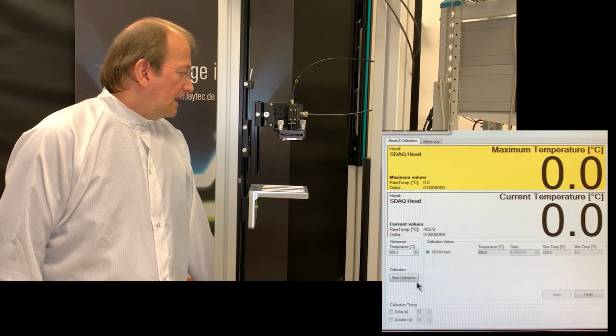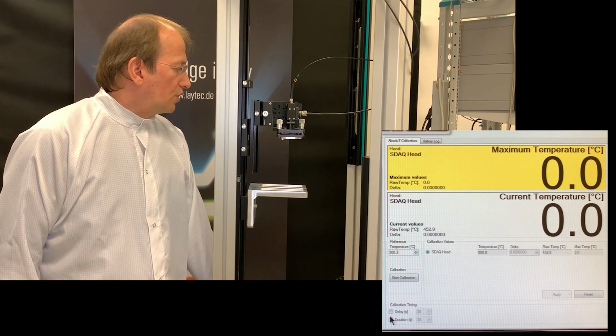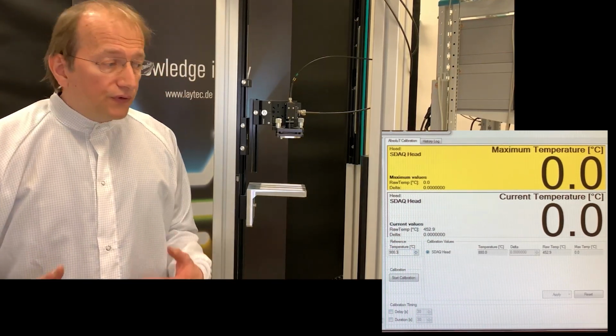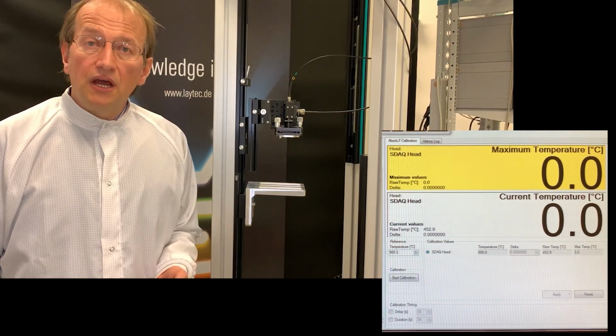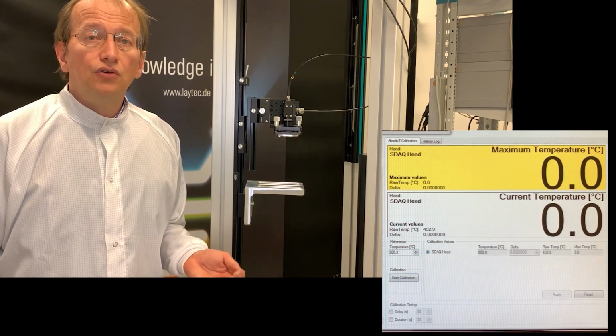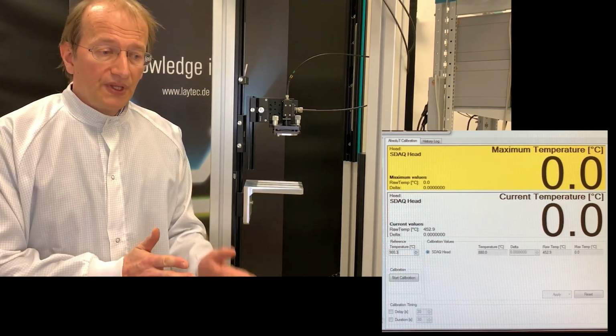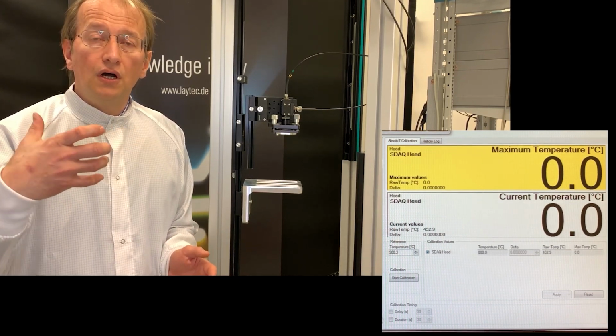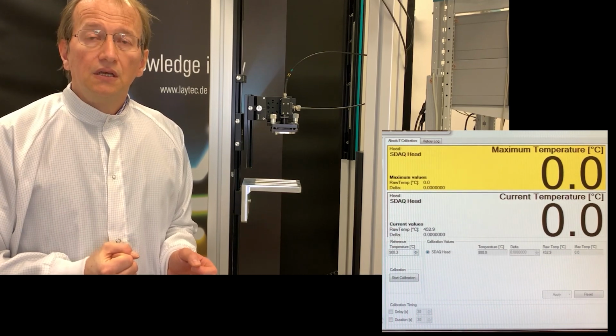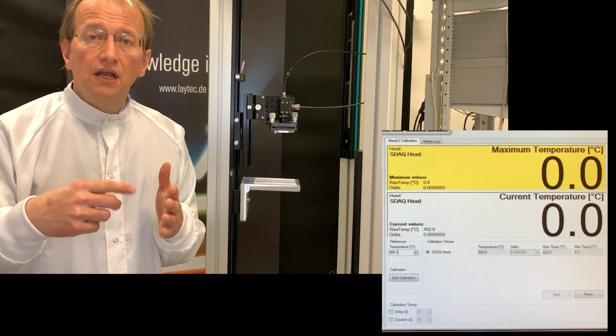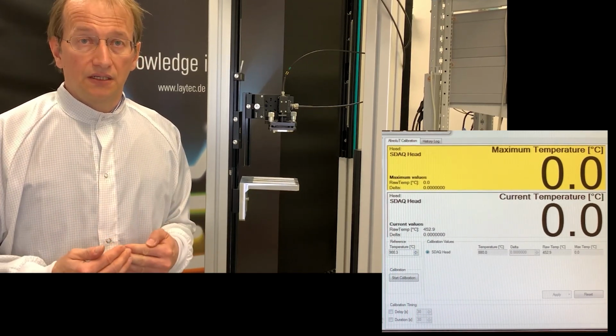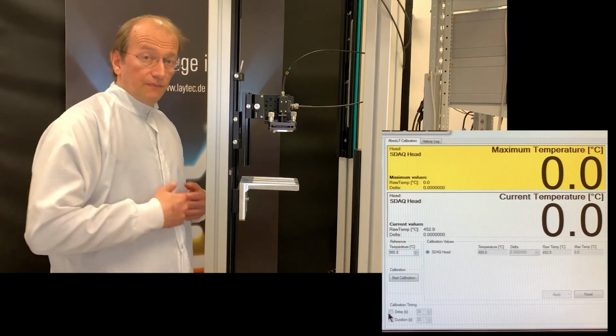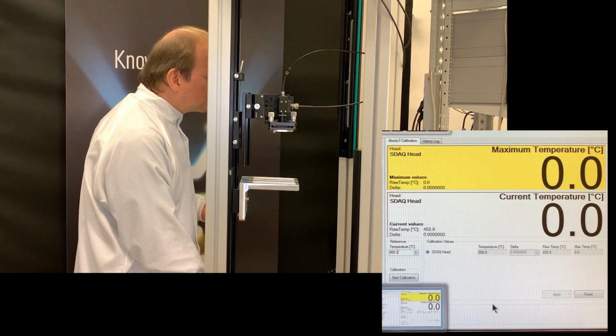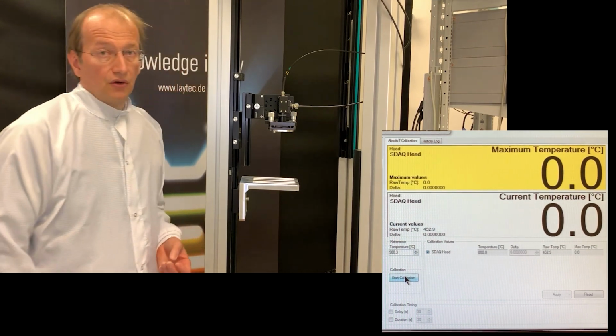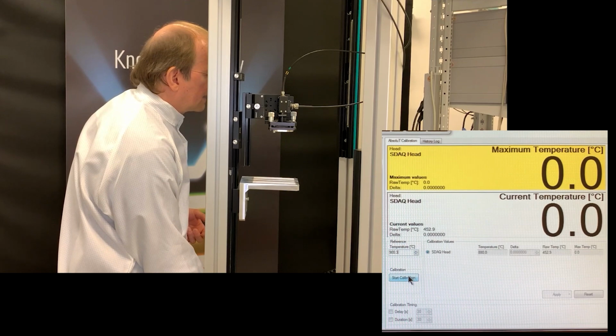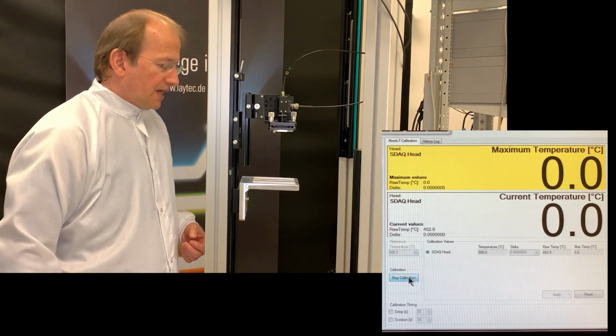and if it's there, we are basically well prepared. And now we have already talked about these two timers. If you work with a colleague, then usually you don't need the timers, but if you need to perform alone, then you could use the timers to set a timer from starting data acquisition until you start to find the maximum signal, and from acquiring this data until it stops the data acquisition, the second timer. So these are these two timers, delay and duration. In the two-person operation mode, we don't need this. So now we press start calibration, and it is acquiring data.